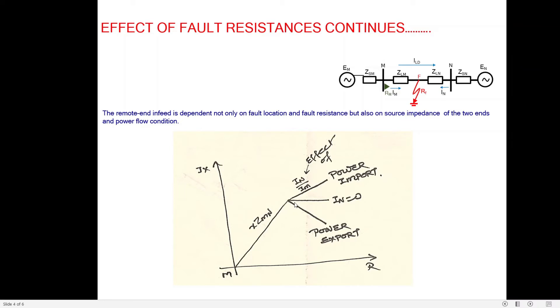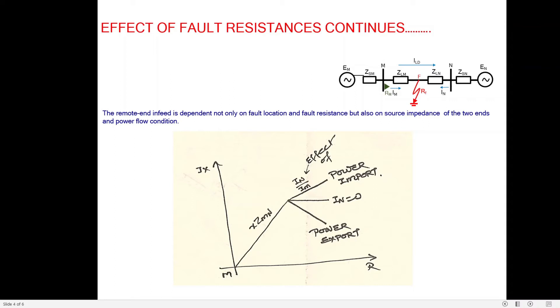When IN = 0 (radial system or no-load line), the effect is purely resistive. But with power export or import, there is a reactance effect. In case of power import, IM lags IN, so IN/IM has a positive effect on reactance — the total reactance measured by the relay increases. In case of power export, IM leads IN, so IN/IM has a negative effect on reactance — the total reactance measured by the relay decreases.